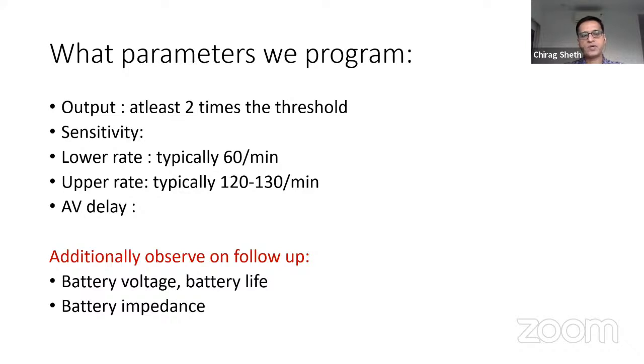What parameters do we program? We program the output, meaning at what voltage the electrical impulse should be given to the myocardium, and it should be at least 2 times the threshold. We program the sensitivity, we program the lower and upper rate. As we discussed earlier, it is between 60 and 130 beats per minute, and we program the AV delay. And additionally, we observe on every follow-up what is the battery voltage, what is the battery life, and what is the battery impedance, because as the device ages after implant, depending on the consumption, the battery is definitely going to decline. Most pacemakers last for 10 to 12 years. And as time progresses, battery voltage goes down and the battery impedance starts rising.